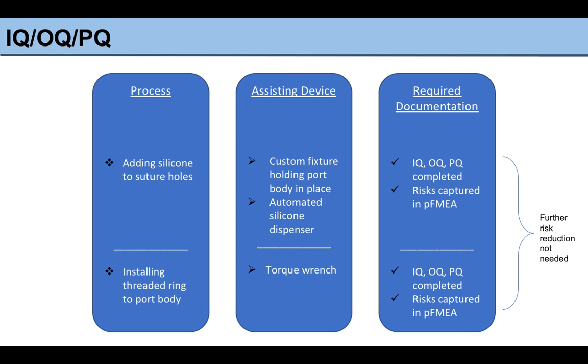There are two processes in our manufacturing procedure that require the use of assisting devices or fixtures. The first process is the addition of silicone to the suture holes of the port body. For this process, a custom fixture designed to hold the port body in place and an automated silicone dispenser will be utilized. The second process involves installing the threaded ring to the port body, which requires the use of a torque wrench. For both assisting devices, the installation qualification, the operational qualification, and the performance qualification were completed based on the protocols that were created.